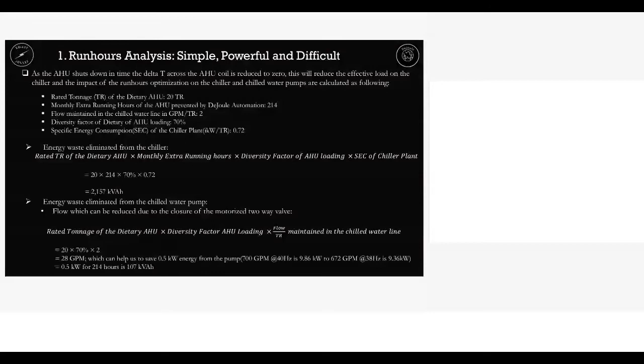We are saving energy from the motor, we are saving energy from the chiller, and now lastly we are saving energy from the pump. If a particular air handling unit is shut down, there is a motorized two-way valve associated with the chilled water line. That valve closes and the flow of chilled water through the AHU cooling coil is prevented. So if the AHU is shut down, the IoT understands this and shuts down the two-way valve, the water flow is prevented and we can save energy from the pump. It is a small value, but still we save energy from the pump.